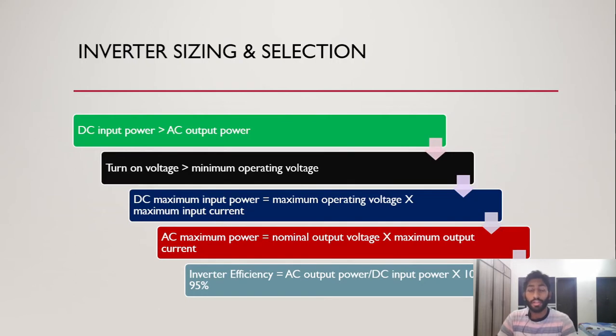The DC maximum input power - if you want to calculate that, you multiply the maximum operating voltage range by the maximum input current in the DC specification. For the AC maximum power output, you multiply the nominal output voltage - let's say if it's 240 volts - by the maximum output current that the inverter will produce.